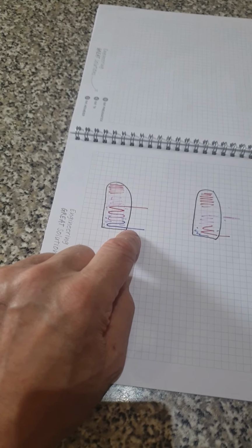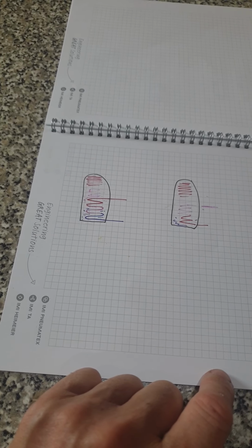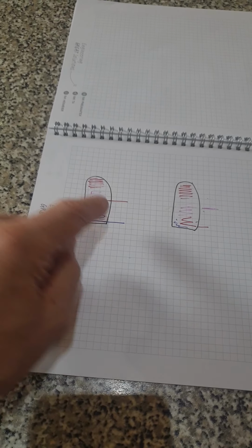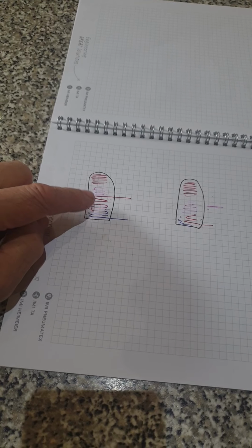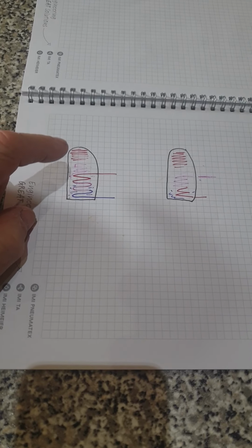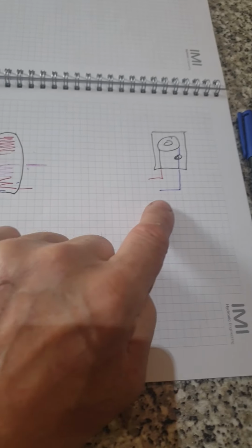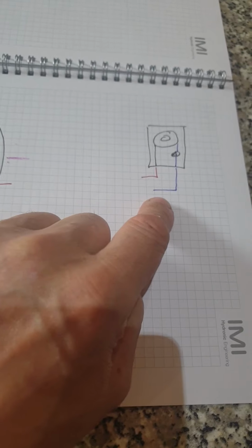That's it. I think that's pretty self-explanatory, and why you should always put the flow in at the top of the cylinder. The cylinder does not control the delta T. A lot of people have this argument many times over. The DT is controlled by the boiler. It's the amount of energy put in.